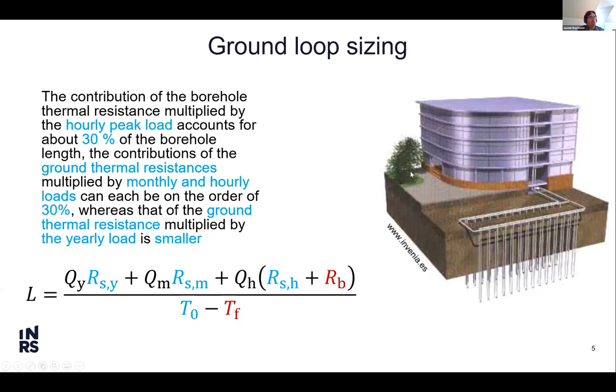And the building energy needs, they are represented by heat pulses that are sent to the ground, the Qs, the average heating or cooling load of the year, and of the peak heating or cooling months, that would be January or July, and the peak heating or cooling load, QH. And this equation is good whether it's for a system designed for heating or cooling.